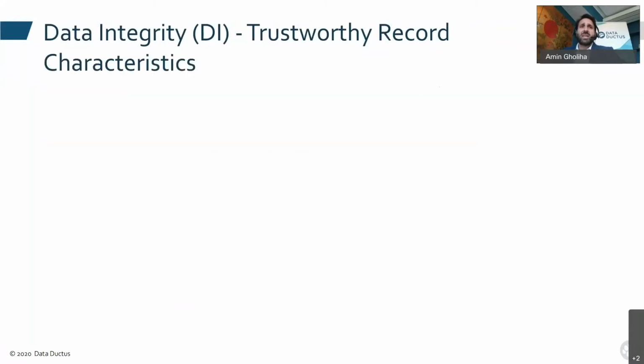And what are the characteristics of a trustworthy data record then? It needs to be reliable, complete, and accurate. With complete, I mean that it needs to have all the metadata around the data: who generated the information, from what type of instrument the data was generated, and it needs to be accurate enough so you can understand it, and you should not rely on additional analysis. You should basically always have the raw data available as well. We will discuss that.